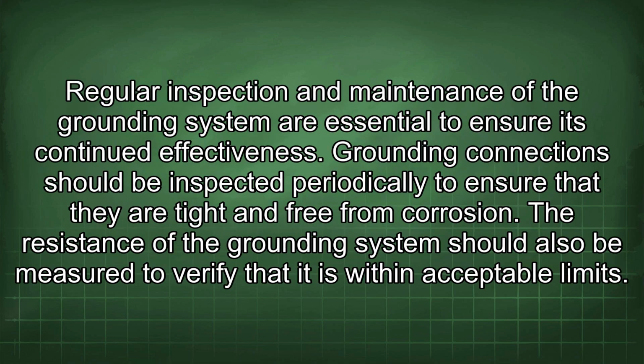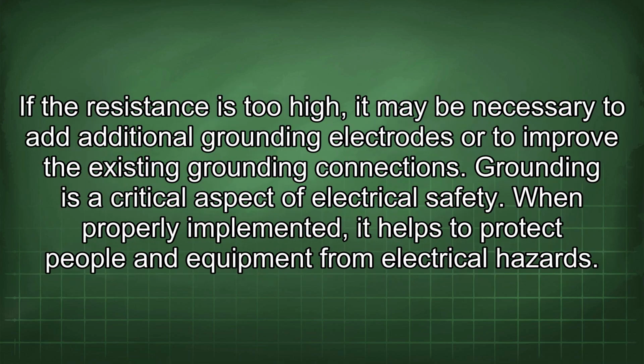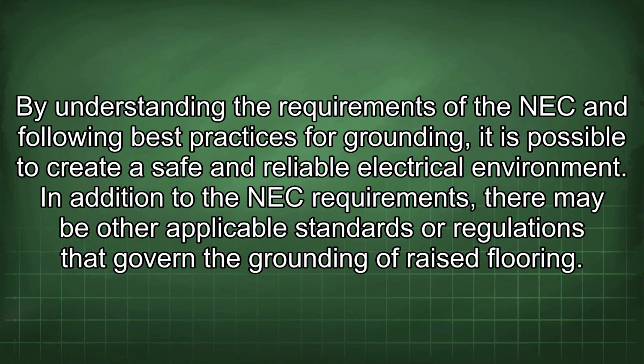Regular inspection and maintenance of the grounding system are essential to ensure its continued effectiveness. Grounding connections should be inspected periodically to ensure that they are tight and free from corrosion. The resistance of the grounding system should also be measured to verify that it is within acceptable limits. If the resistance is too high, it may be necessary to add additional grounding electrodes or to improve the existing grounding connections. Grounding is a critical aspect of electrical safety. When properly implemented, it helps to protect people and equipment from electrical hazards. By understanding the requirements of the NEC and following best practices for grounding, it is possible to create a safe and reliable electrical environment.